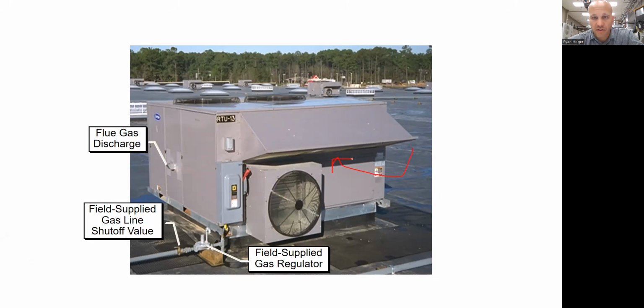All right, it sucks outside air in that way. And it also has a damper in here typically where it can open more or less, and it can open more when you want to get free cooling. What does that mean? That means the indoor space wants cooling, but it's mild outside. Maybe it's like 60 degrees outside or something like that. Well, if it's 60 degrees, why run my compressor in this unit? I'll just go ahead and open this damper more and just suck more cold air in, right? More means I get 3 hours instead of 1 hour. So suck more cool air in and free cool the space.